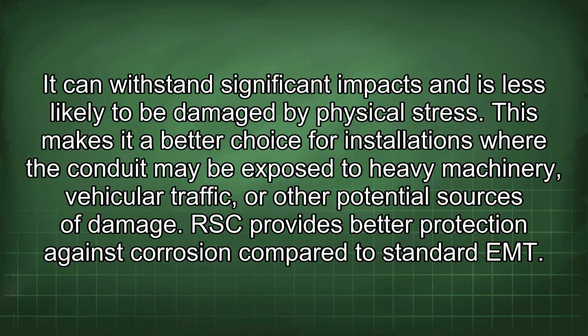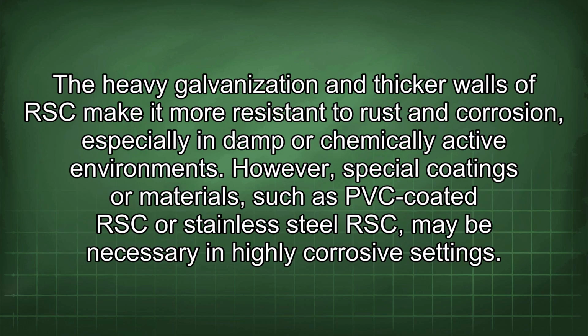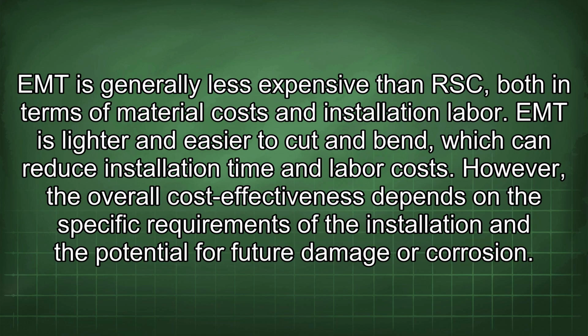RSC provides better protection against corrosion compared to standard EMT. The heavy galvanization and thicker walls of RSC make it more resistant to rust and corrosion, especially in damp or chemically active environments. However, special coatings or materials, such as PVC-coated RSC or stainless steel RSC, may be necessary in highly corrosive settings. EMT is generally less expensive than RSC, both in terms of material costs and installation labor.